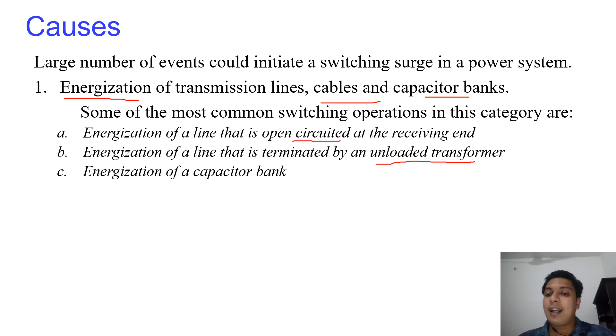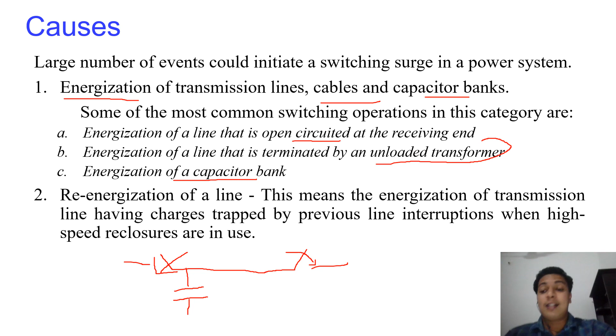Now we should also see the re-energization of a line. Like, we isolated a line from the two sides. Let's say there was some work going on, and you just isolated that transmission line from two ends. What do you think, will there be some potential over the transmission line or not? The fact is that there will be, and because of that, whenever you are re-energizing this line again, it can cause a transient or overvoltage. So this is another thing that can cause overvoltage.